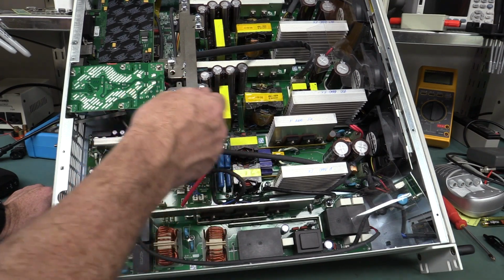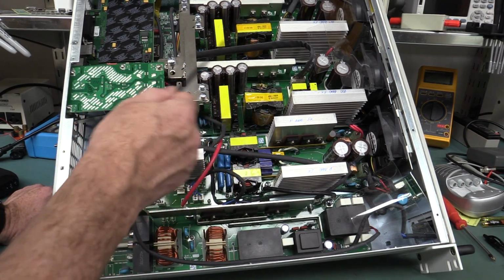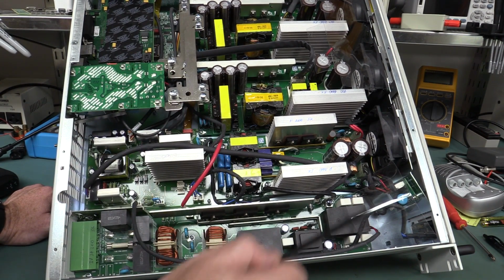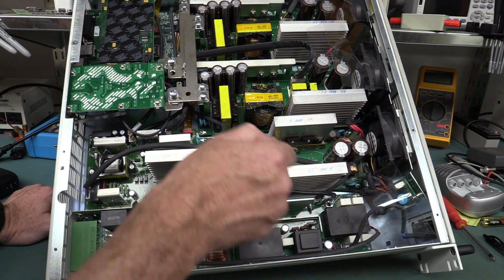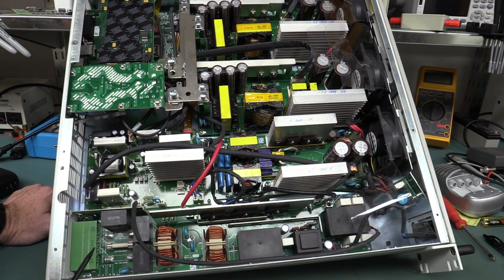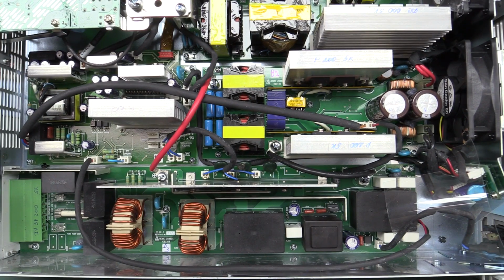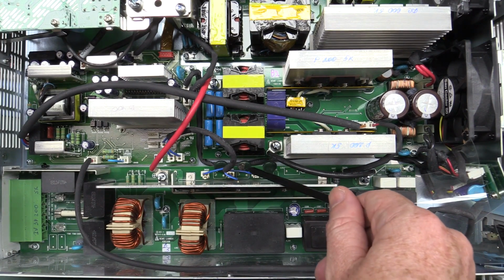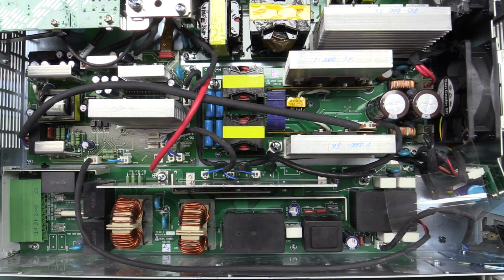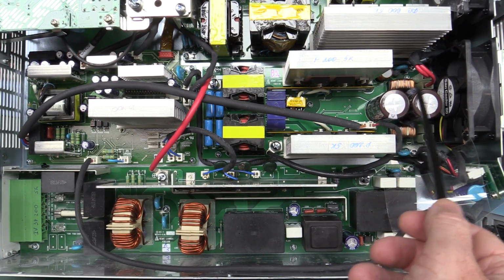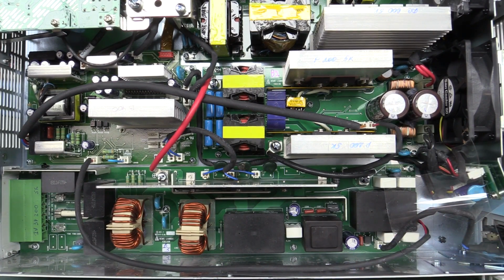After that, I wouldn't expect anything on the secondary side over here to be blowing. So if anything's going to be blowing, it's the primary side over here and all this power factor correction stuff in here. So who knows, we might have got lucky and the fuses here and the MOVs actually protected. Or MOV, singular, well the others would have kicked in as well, but they didn't have their ass blown out of them, so all the energy was directed to that middle one by the looks of it. But they could have taken out the fuses quick smart before the energy could build up in these caps here, and damage anything else. That's what you'd be hoping anyway.